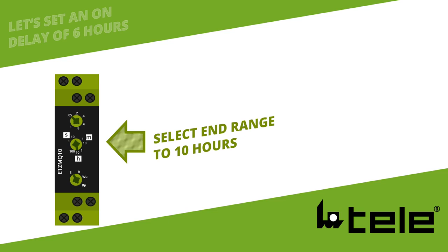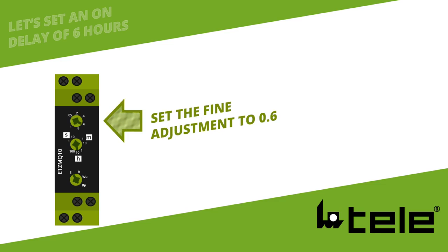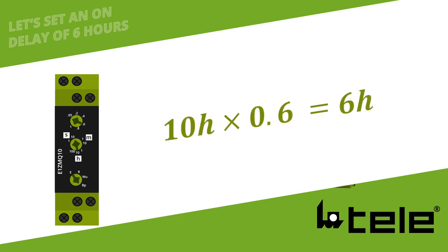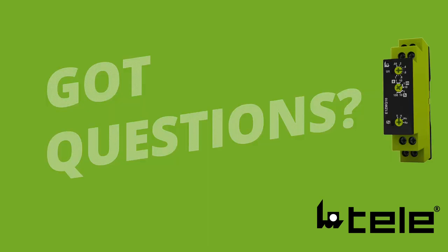Now, always be careful that you don't overturn these dials because they can be very sensitive sometimes, especially if you rotate them 360 degrees. They don't like that at all. Sometimes these settings are also done by dip switches, but in our circumstance, the fine adjustment is done by the top dial and you select the percentage of that. In our circumstance, that would be 0.6, so 10 hours times 0.6 equals a 6-hour delay.